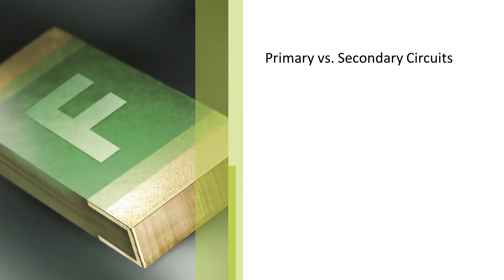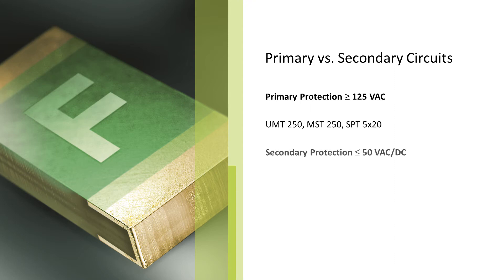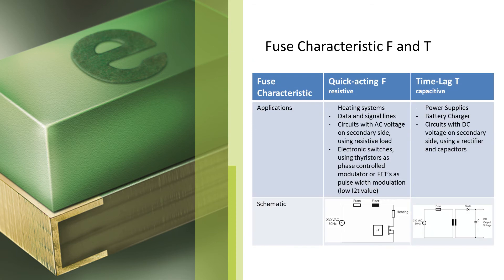Schurter is specialized in non-resetable fuses for primary protection of typically 250V AC, and also for non-resetable fuses for secondary protection of up to 50V AC or DC. Non-resetable fuses are available in different characteristics. Quick-acting fuses open very quickly in the event of a short circuit. They are often used for resistive load types with a power factor of around 1. Typical applications are heating systems, data and signal lines, or applications with a pulse load.